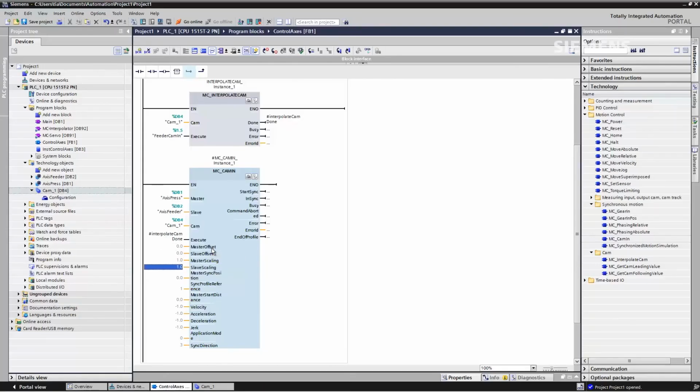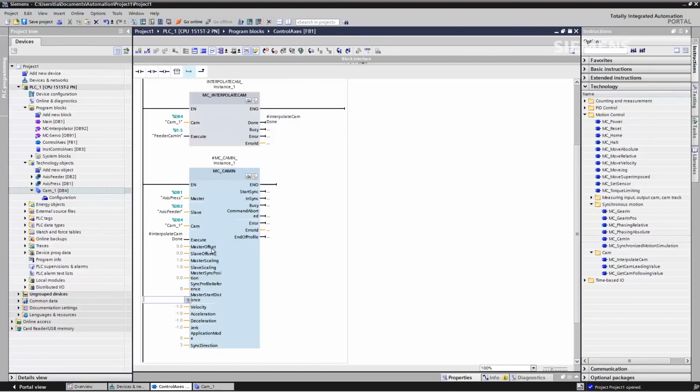There are also options to adapt, move, and scale the cam disk. For example, on cam disk pitch to 1, which is naturally also an option. In our case, however, we're sticking to the basic settings. The question still arises, how do we perform the coupling? This is performed either by specifying the path or by specifying the dynamics. We choose to specify the dynamics, and we select 0, but we leave the default settings of the dynamics as they are here.